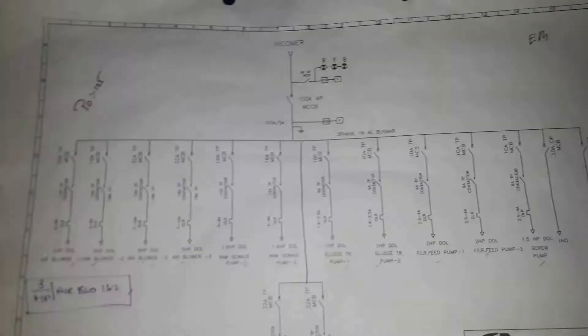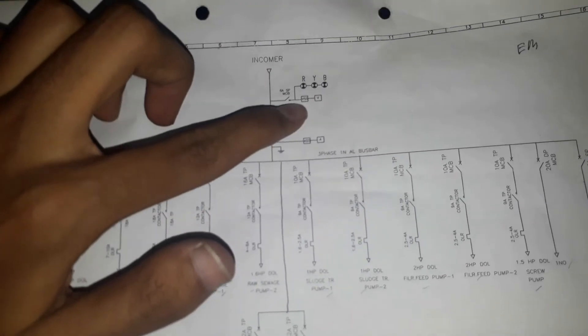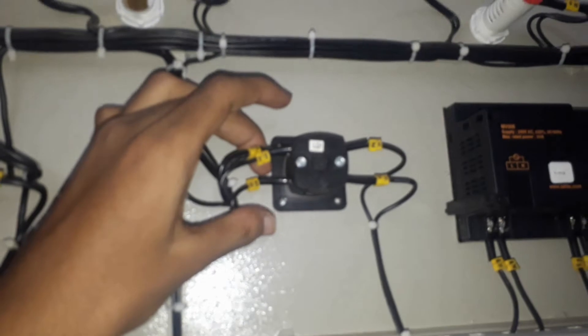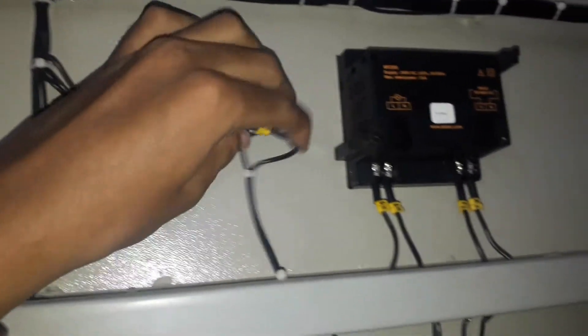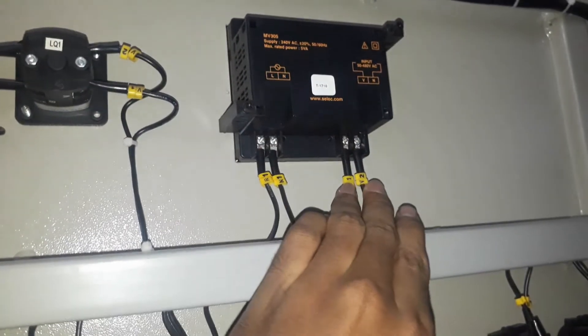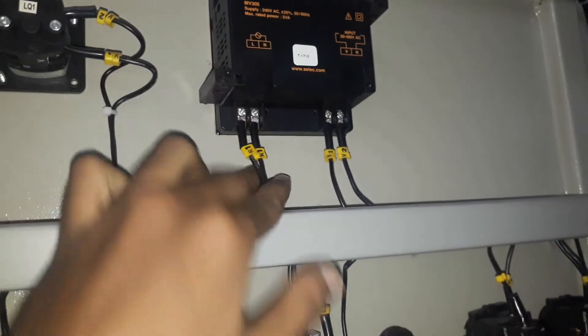This one is the main MCCB. Here you can see the SLD of this panel. From the incomer we are connecting a voltmeter selector switch and a voltmeter. The three phases R, Y, B are connected to the voltmeter, and the two outputs from the voltmeter selector switch — K1, K2 or V1, V2 — are connected as input to the voltmeter. Auxiliary supply R and neutral are also connected to this voltmeter.